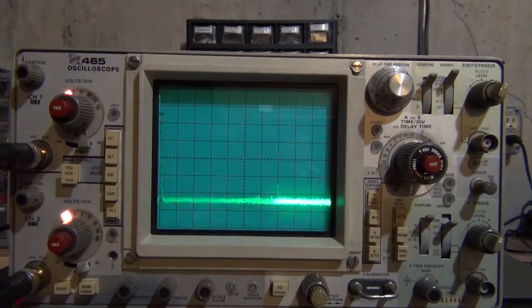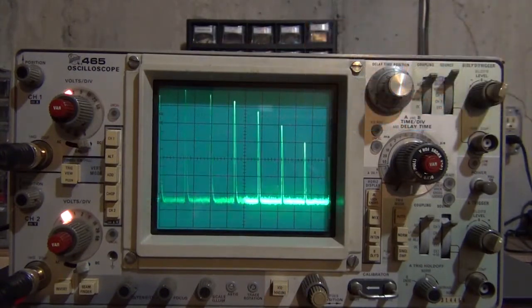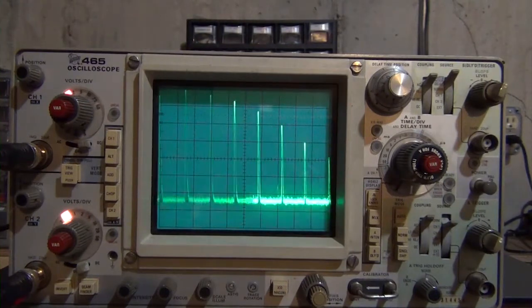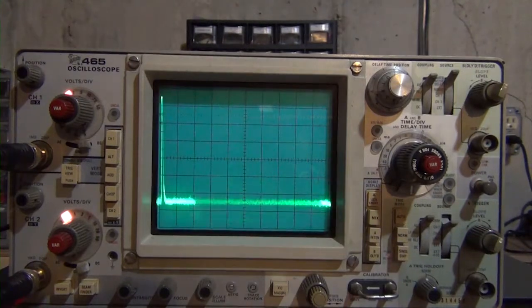I mentioned earlier that the SA also has a calibrator function. So what I've done, I've reconnected the input to that calibrator, and I'll turn it on now. And it's very basic. It's just a crystal with overtones at 10 megahertz all the way out to the limit, about 70 megahertz. And it's not a fixed amplitude, obviously, for each overtone, but what I have done is just record using a separate meter what each of those peaks are.